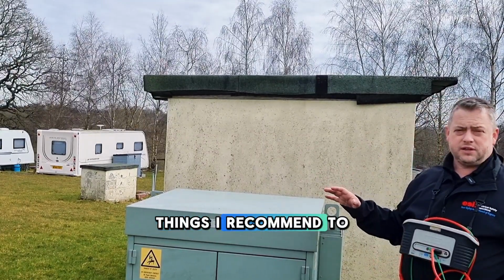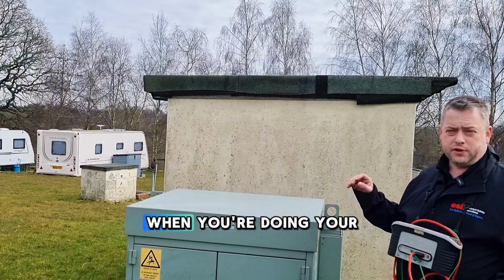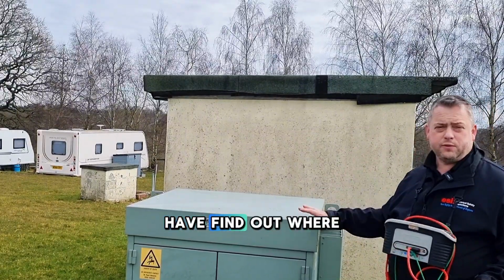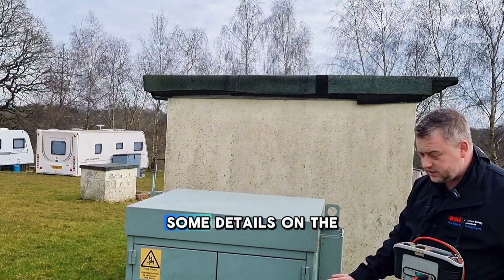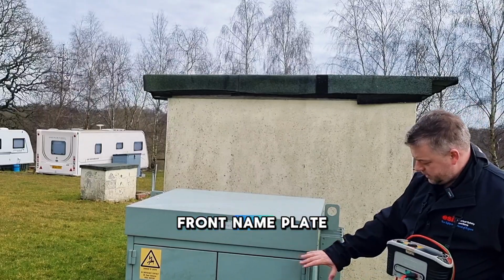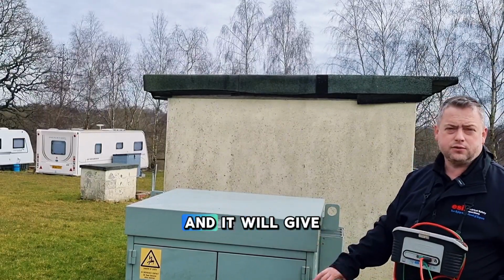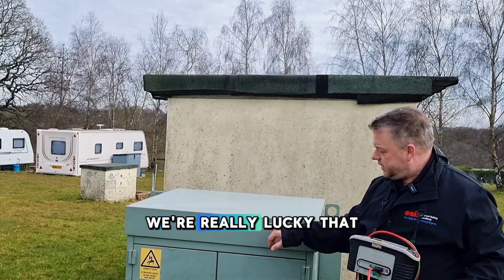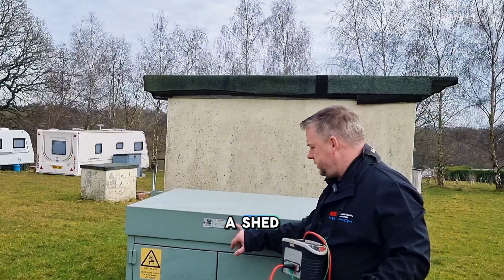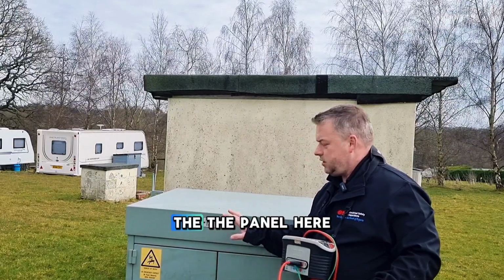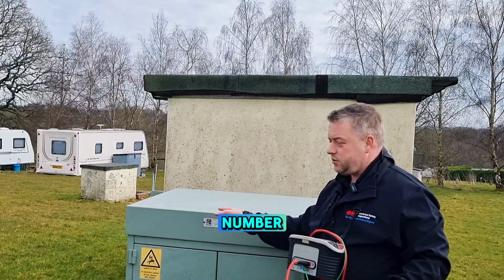So one thing I recommend is to always take a look when doing your electrical inspection: find out where the substation is and note some details from the front nameplate. It will give you the name of the site and the transformer number. We're lucky this one isn't inside a shed, so we can get details off the panel - the make, the model number, the size.